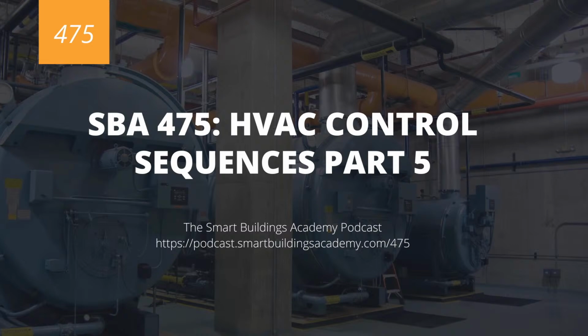Boiler enable is real simple. You just have a relay. You turn it on via a set of contacts. Boiler pump command, pretty straightforward as well. The big thing is we tend to interlock flow status with the boiler enable. So we will enable the pump and get flow status and then enable the boiler. Sometimes the boiler has its own flow status as well as its own circulating pump.